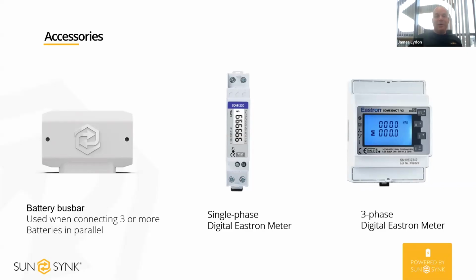So with the bus bar, if you've got those six batteries, they are all going to connect on typically 25 mil square into the bus bar. And then from the bus bar, dependent on the size of the inverter, if it's a 12 kilowatt hybrid inverter, let's say you might have 50 mil or up to 75 mil square. But that means that all the batteries are feeding off the same plate. We're not going into the first one and it's then trickling down. All that power is coming down into the batteries.